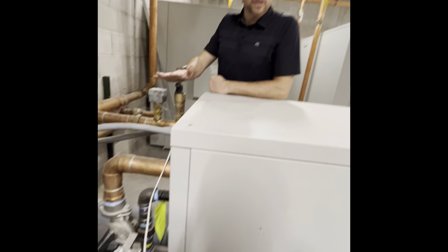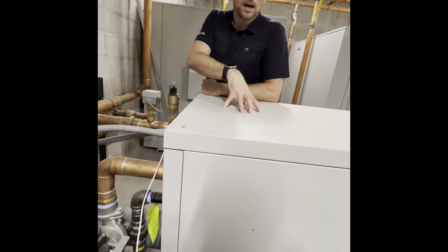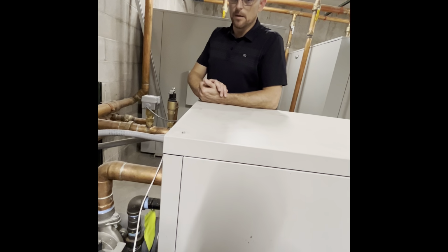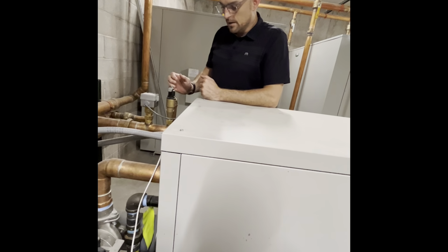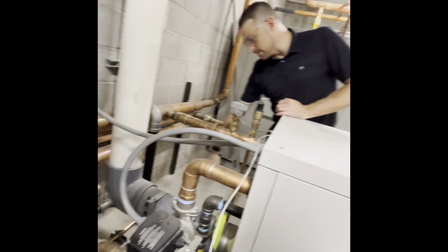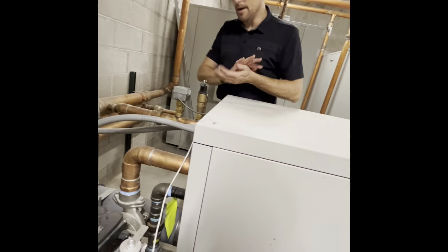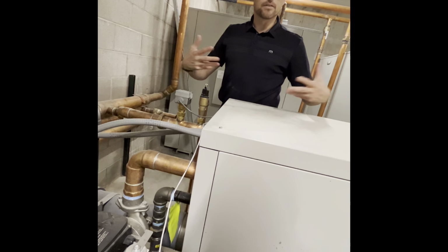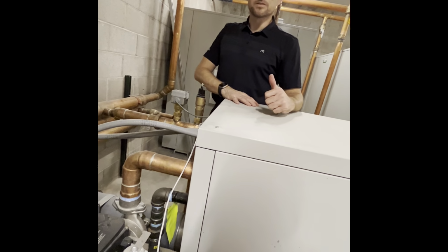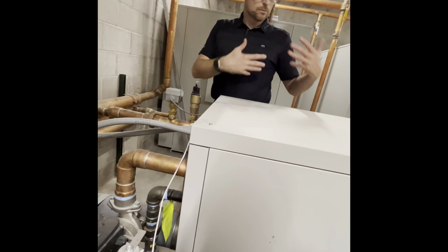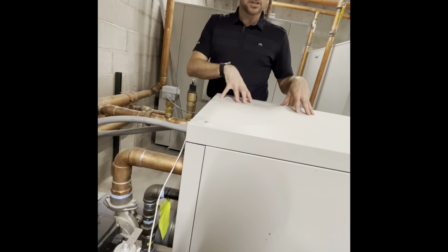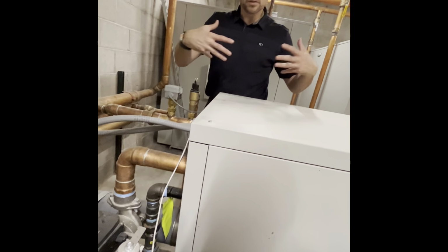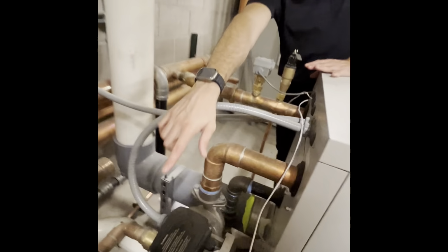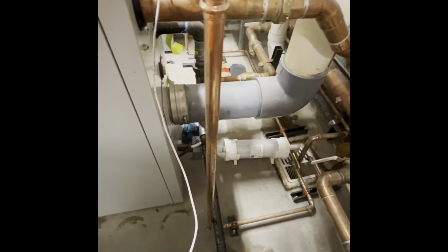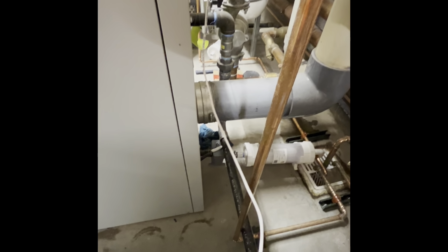This is a temperature and pressure relief valve. If anything's exceeded in here as far as the pressure or temperature above a certain threshold, for safety precautions, it's going to purge it out of here, and that's just going to run down this piping and down into the drain. Again, like I said, this is a condensing unit, so it is going to have condensate, just much like a cold Coke can or something. Everything's going to be sweating. So that's what really gives it its efficiencies, because it is a stainless steel heat exchanger, so you want that condensate buildup. But what's happening down here on the very lower part, you can actually see right there where it's piped out, there's a trap that allows that gray box, that's what allows that runoff from the heat exchanger, that condensate, to be able to flow through there.